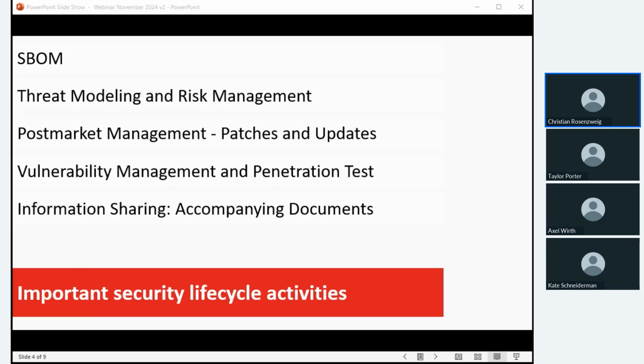The big difference between the European and US systems about that vulnerability management process is that the FDA requires so-called metrics. So they want to know, for example, the percentage of identified vulnerabilities that are updated or patched. That's the so-called defect density. Or they are focusing on the duration from vulnerability identification to when it is updated or patched. So you have to measure the time between getting aware of a vulnerability and providing an update or patch.